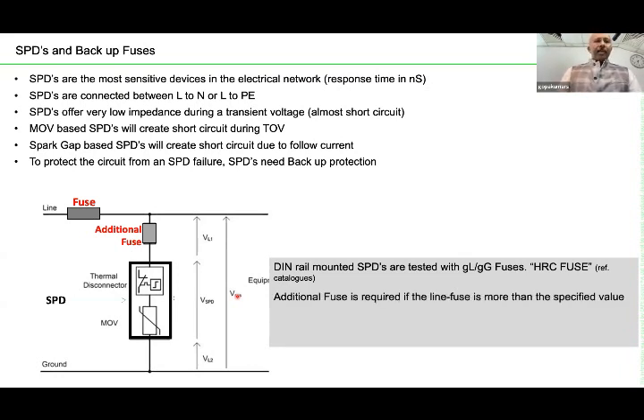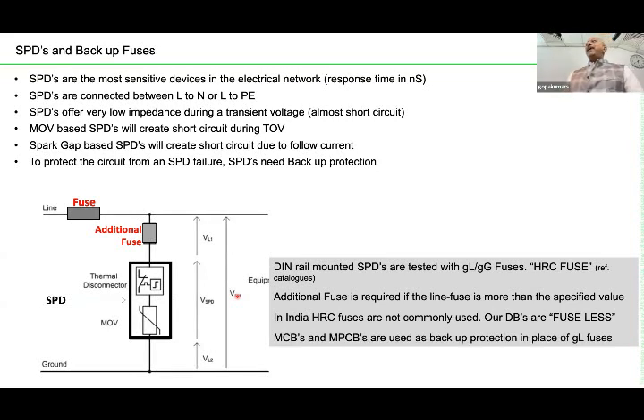Now, the users are always confused about where to put the HRC fuse and how to select the HRC fuse, because the manufacturer has simply told that my device needs an additional backup fuse if the line current is more than 125 amps. I hope you got it. The SPD manufacturer will tell that this device needs an additional backup fuse once the line current is more than 125 amps. This is the statement from the manufacturer.